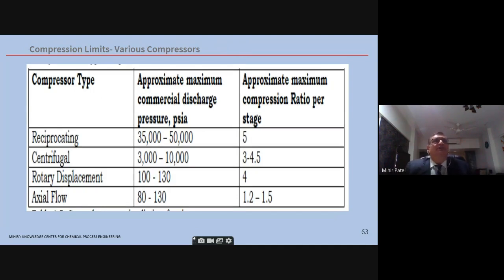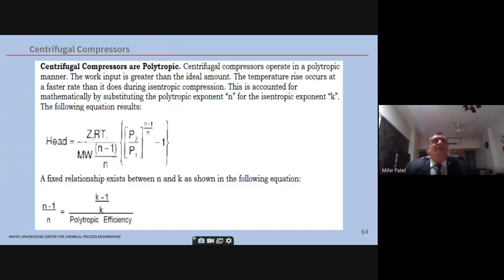Compression limits. So this is important. Reciprocating compressors, as you can see, can have very high discharge pressures, about 5 compression ratio per stage. The centrifugal compressor, you can see, can go up to 10,000. Axial flow, the delta P is very less, so 1.2 to 1.5 on the compression ratio. And the centrifugal compressors are always polytropic in nature. This is very important. Okay. So the centrifugal compressor and axial compressor are always polytropic in nature. They have more loss on the enthalpy side than the reciprocating compressor, which is isentropic. So as one can see, the interrelation of the polytropic n coefficient versus the isentropic k coefficient is shown in the formula below.